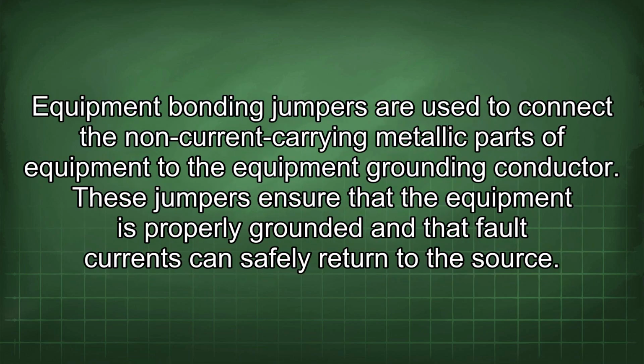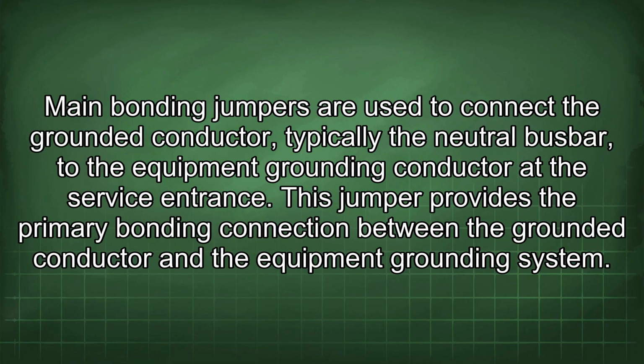Equipment bonding jumpers are used to connect the non-current carrying metallic parts of equipment to the equipment grounding conductor. These jumpers ensure that the equipment is properly grounded and that fault currents can safely return to the source. Main bonding jumpers are used to connect the grounded conductor, typically the neutral busbar, to the equipment grounding conductor at the service entrance. This jumper provides the primary bonding connection between the grounded conductor and the equipment grounding system.